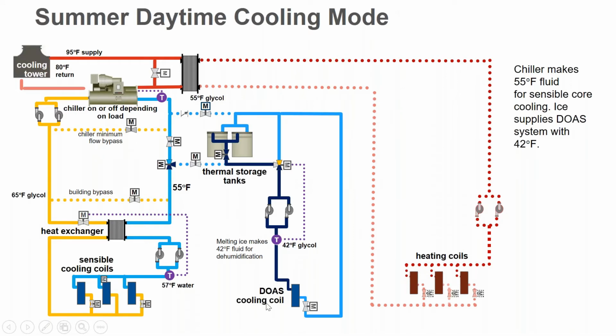Then you also have the DOAS coil. That's where the latent energy is being taken out. You can very easily supply that from the thermal storage tanks, giving you a 42 degree glycol temperature going to those coils. And so you have a nice cold coil here, cold being supplied by the ice melting. And so you've separated out the DOAS cold coil from the warm coil. Now, if the system wasn't balanced right, you could certainly have the chiller operating and some of the cooling connecting over to the tanks, but I won't go into that mode.